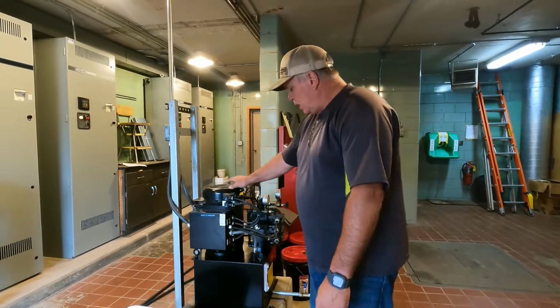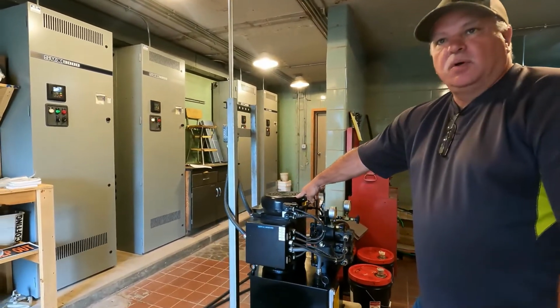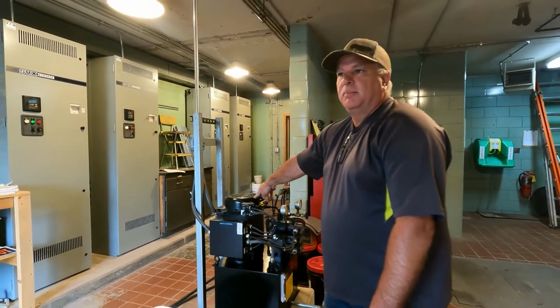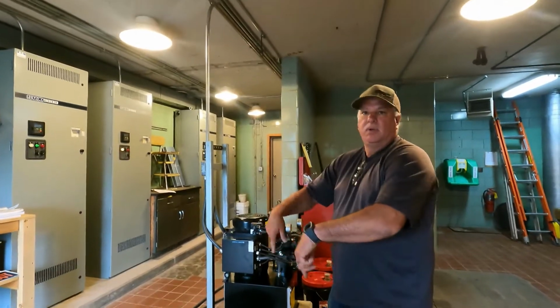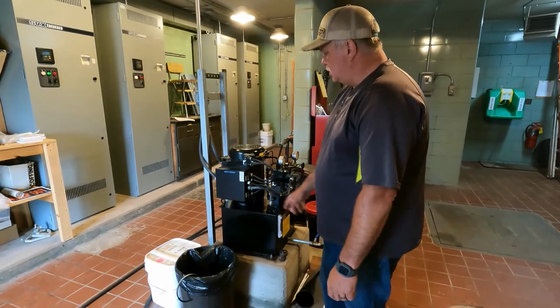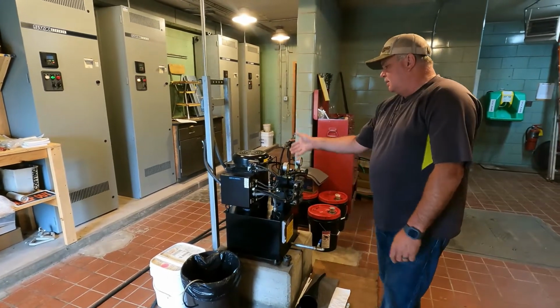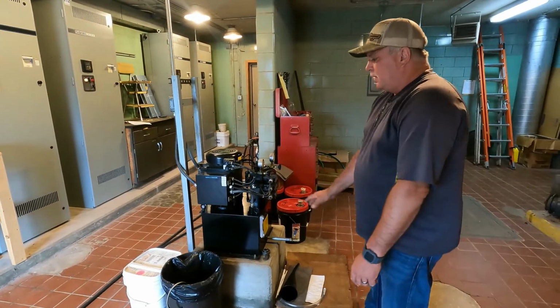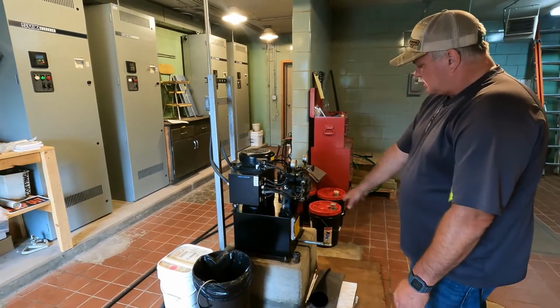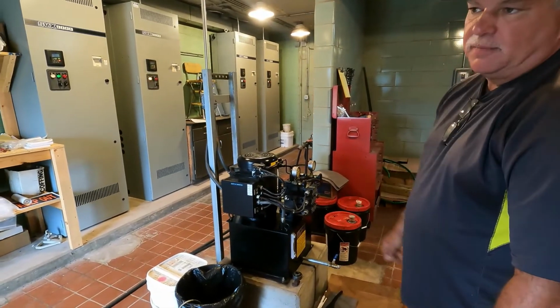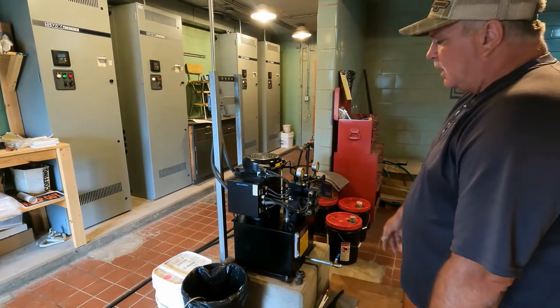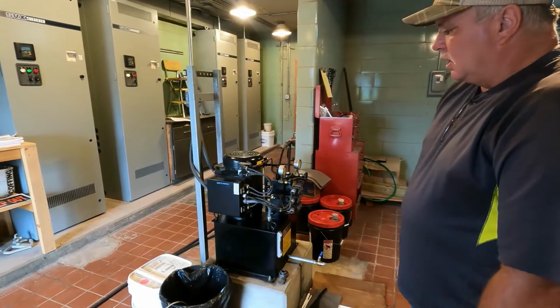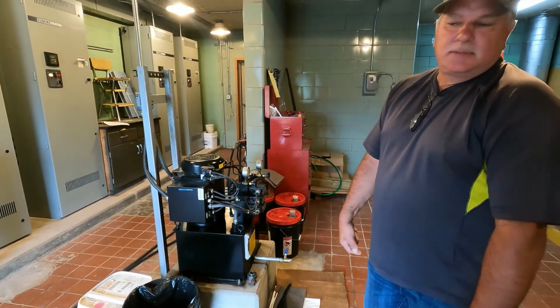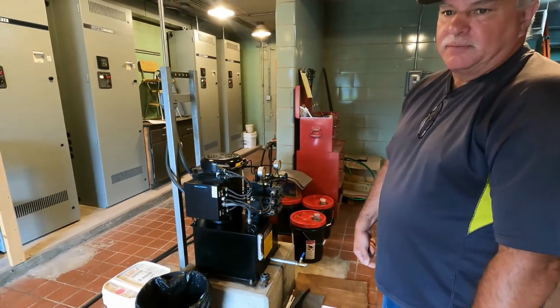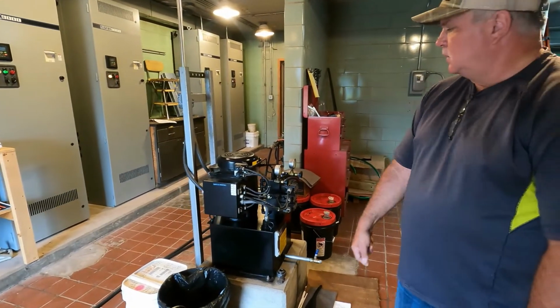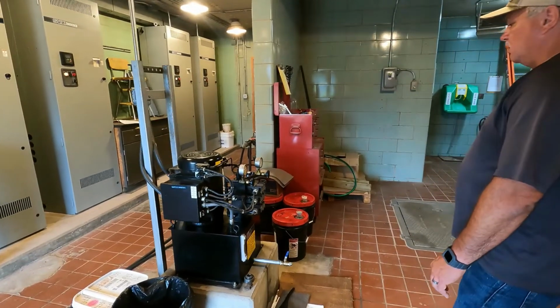Here, what we call a hydropack, is the actual hydraulic pump that's operating the muffin monster. It's turning the teeth of the muffin monster in the channel. There are a couple of grease fittings on the motor that periodically have to be serviced. The fluid inside the pack itself has to be serviced to proper levels. There are alarms for grinder jams, things like that. We'll be notified at the plant if the grinder is jammed or if it's low on oil. So there are quite a few different alarms as well.